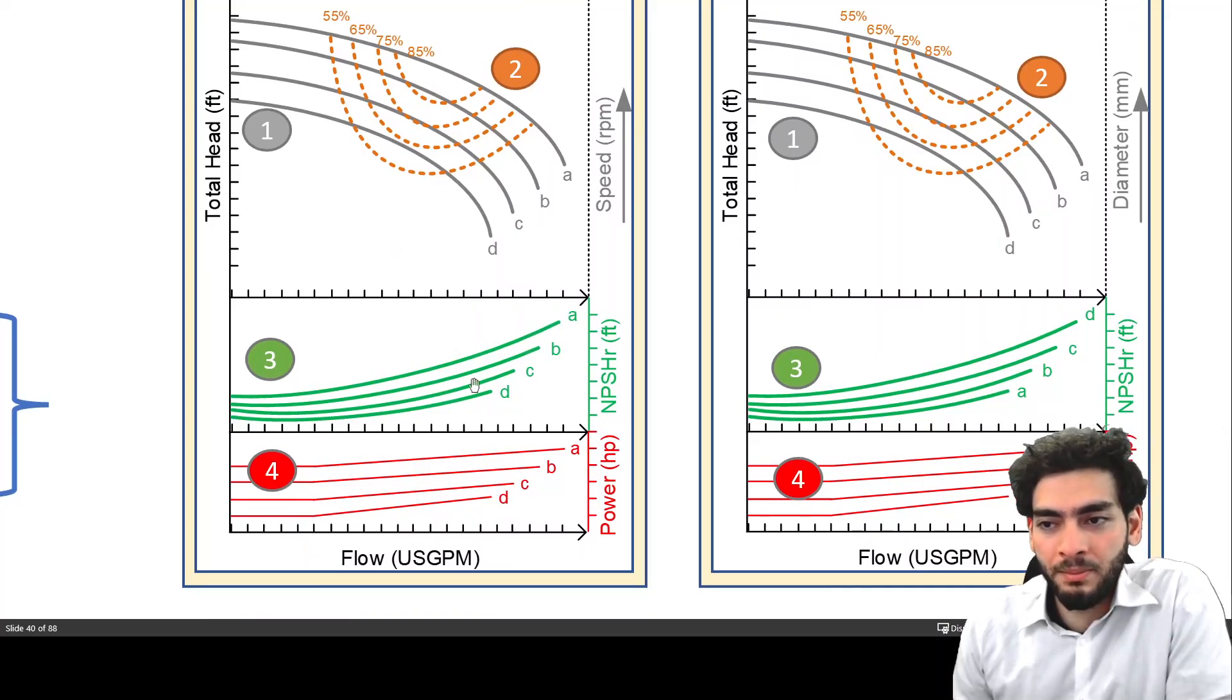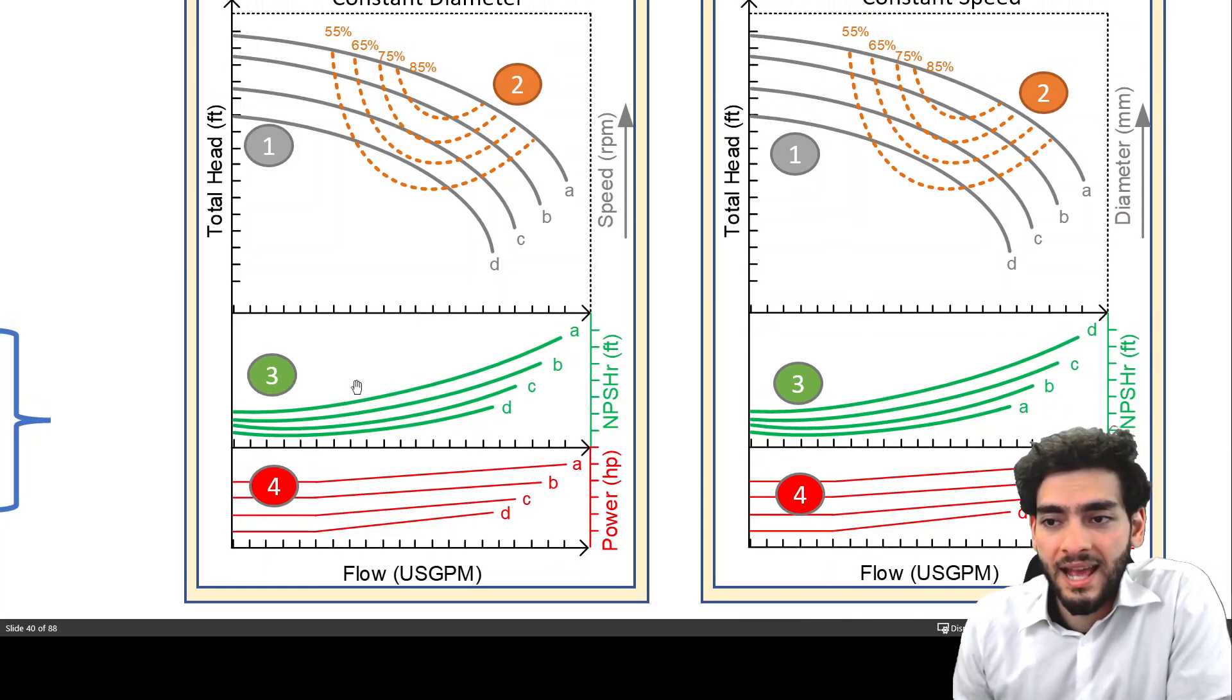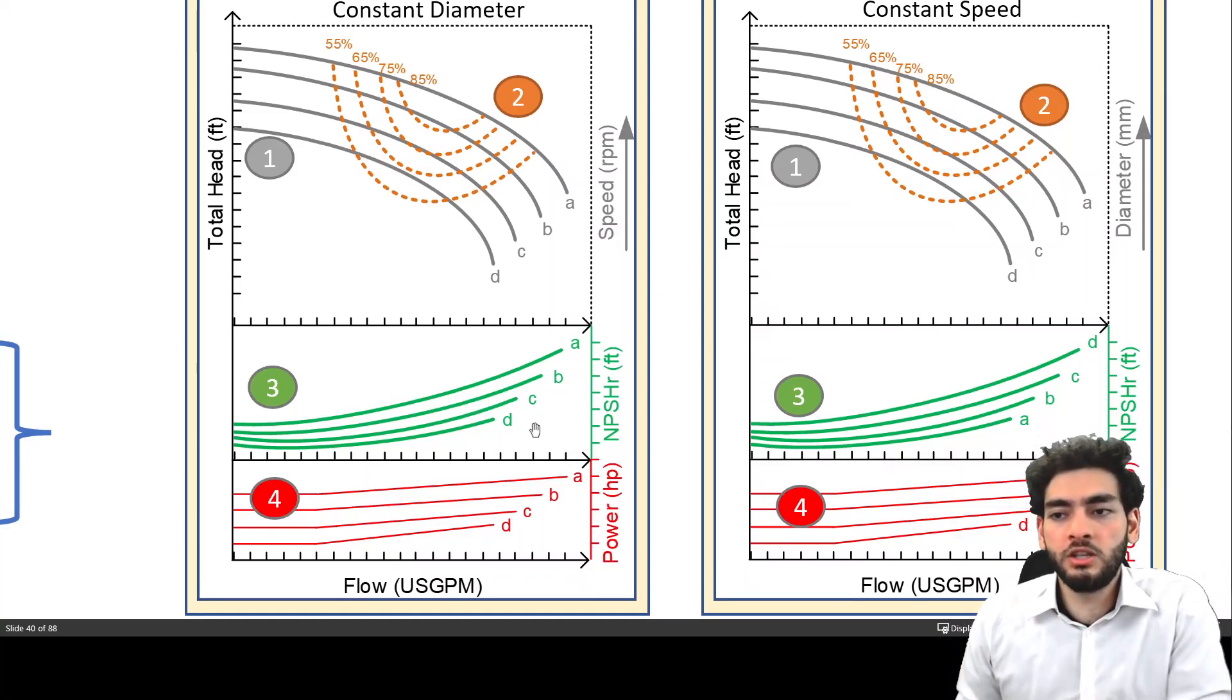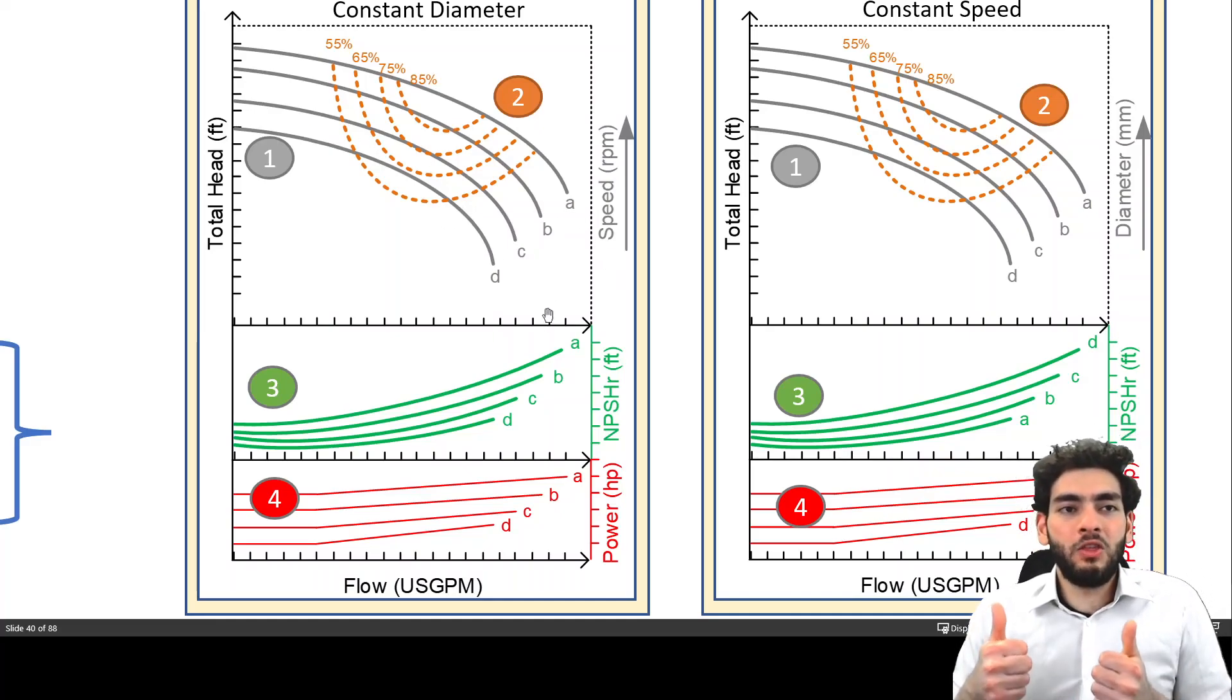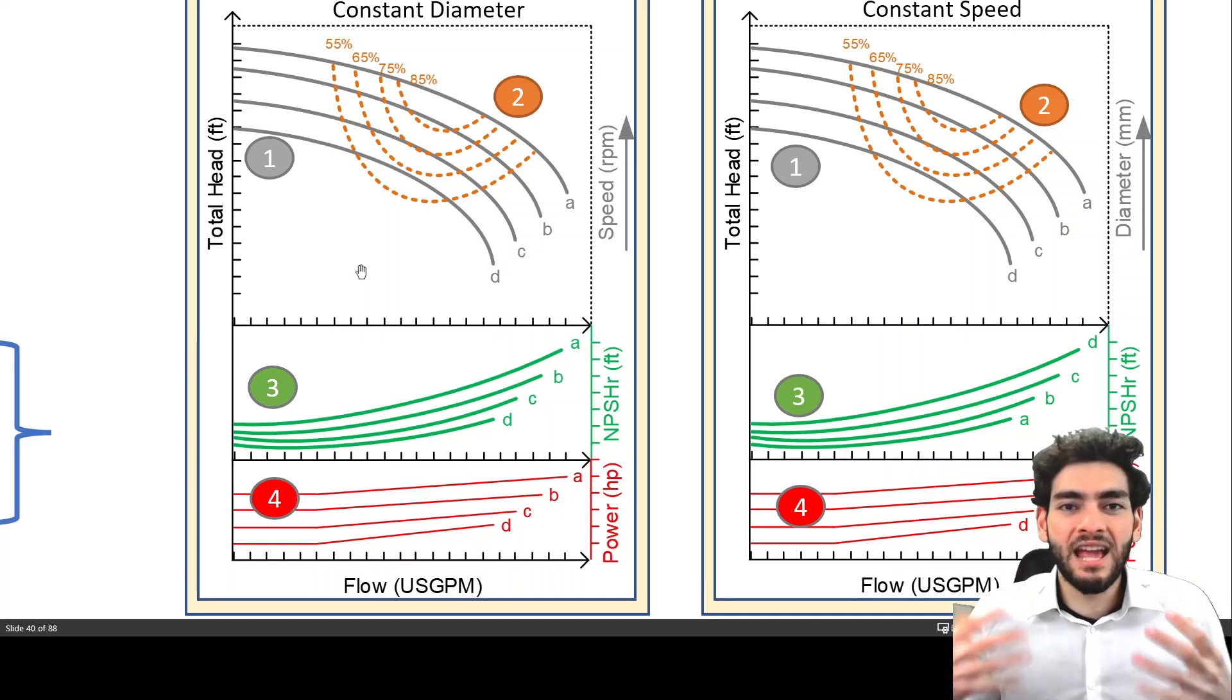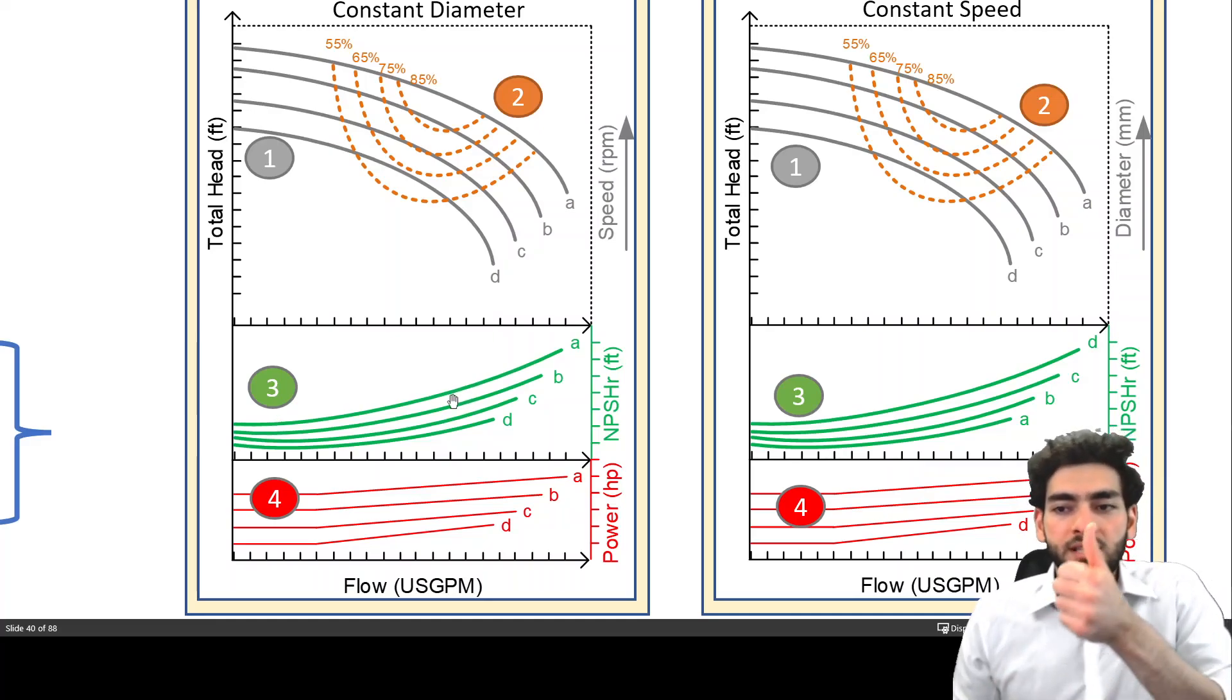They will also provide you with the NPSHR curves, which is the net positive suction head required curves. And as you could see, the NPSHR curve changes depending on what speed you're operating at. So as you increase the speed of the impeller, such that you have more head and more flow rate in your system, the NPSHR curve also shifts upwards as a result.